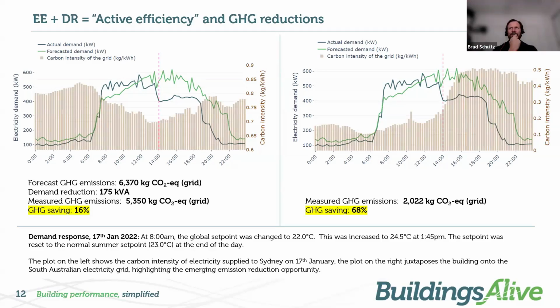Yeah, it's interesting, there's a few things. The control strategies are essentially set point adjustments. Normally you might have a comfort range - a lot of buildings might operate at 22.5 degrees, but really you could go from 21 to 24, and that's within what should be an acceptable comfort range. So if you put it down to 21 degrees for a few hours, to the point that the thermal mass of that building takes on that temperature, when you drop it back to 24, that thermal inertia will carry it through for the rest of the day, like we've seen there.